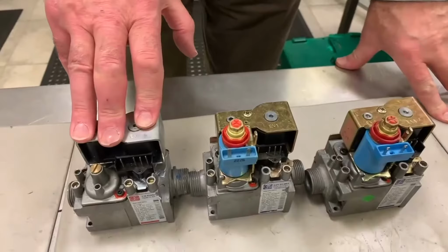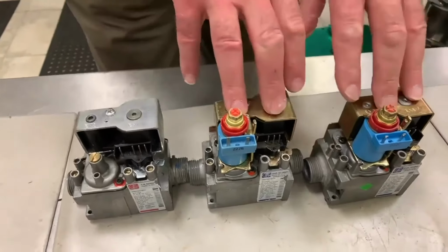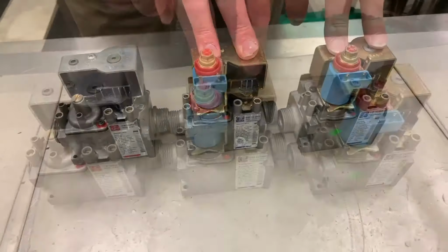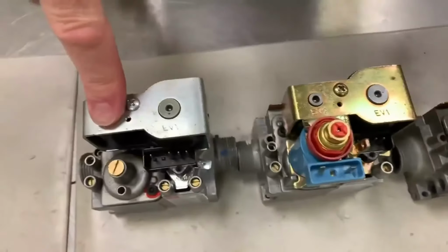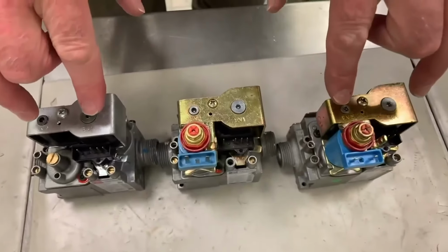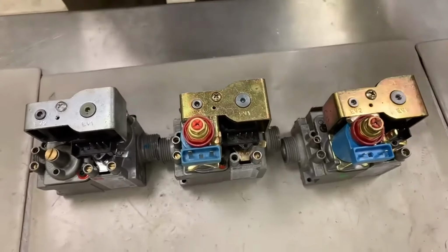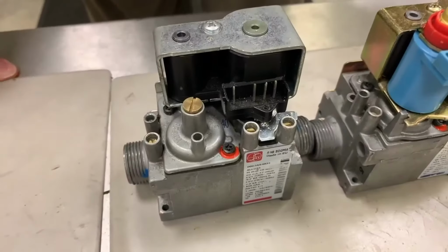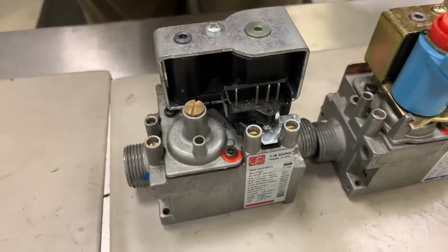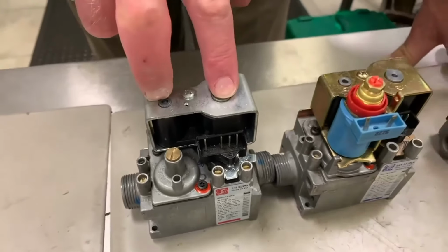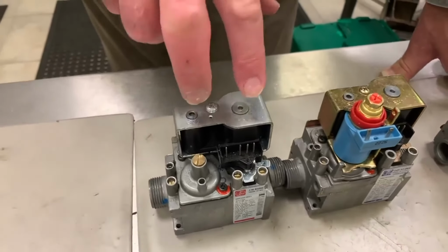There we go. This is a gas valve off a current A rated boiler. These will be gas valves off a B rated boiler. Solenoid pair here, here and here. They are the solenoids that lift up the two plungers that allow gas to pass through. So they operate in a different way, but the solenoids are tested exactly the same way. They're the same solenoids.